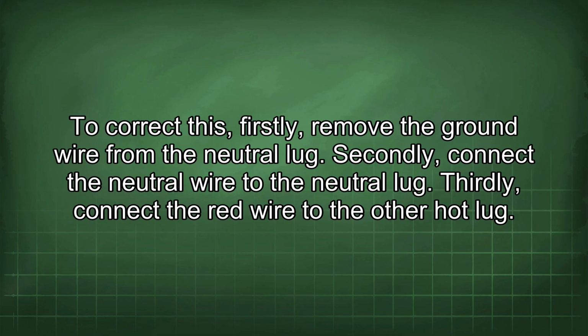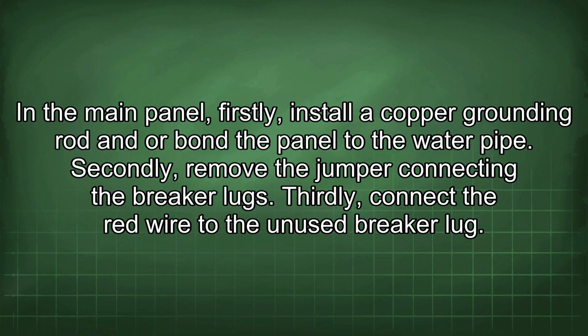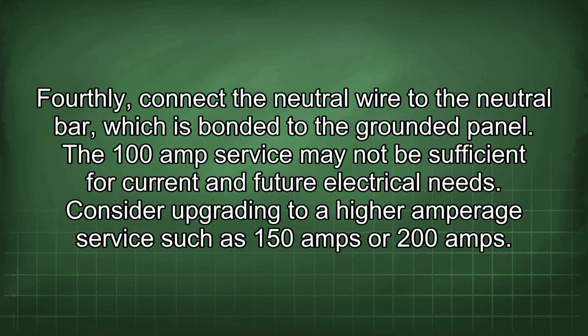To correct this, firstly, remove the ground wire from the neutral lug. Secondly, connect the neutral wire to the neutral lug. Thirdly, connect the red wire to the other hot lug. In the main panel, firstly, install a copper grounding rod and/or bond the panel to the water pipe. Secondly, remove the jumper connecting the breaker lugs. Thirdly, connect the red wire to the unused breaker lug. Fourthly, connect the neutral wire to the neutral bar, which is bonded to the grounded panel.